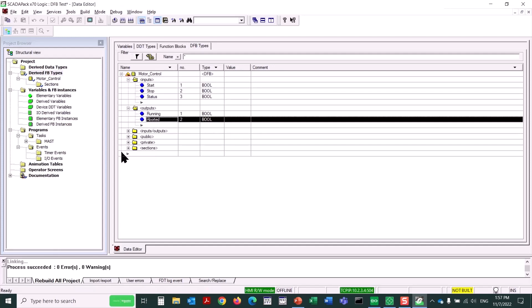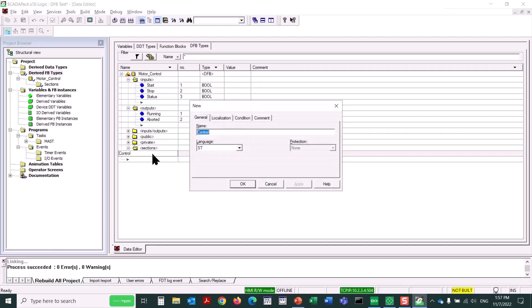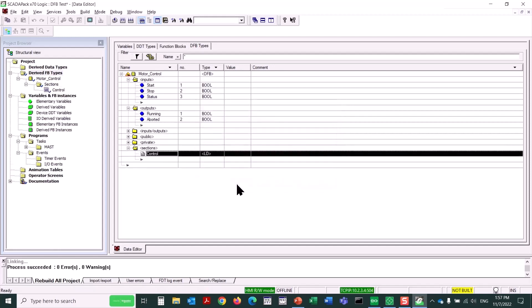Next, I'll expand the Sections folder, and we'll create a logic section. We'll double-click on the first free line, and call this Logic Section Control, and then, when I hit the Enter key, up pops a dialog, and it asks what logic language I would like to use. I'm going to pick Ladder Diagram, because that's somewhat similar to the way Telepace is programmed, and then click OK.